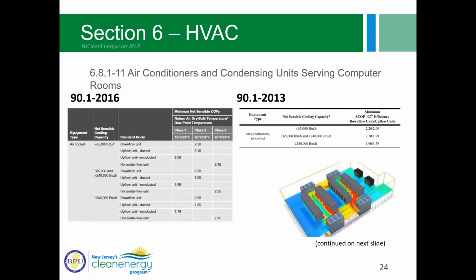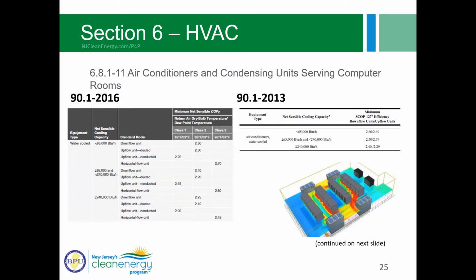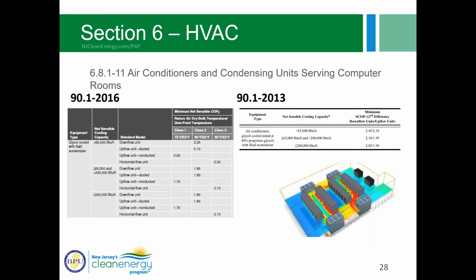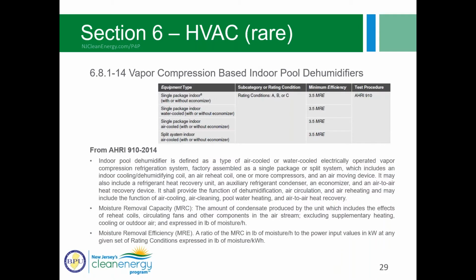that we're specifying. Same table here, this is for water-cooled units. So similar expansion between all the types of units. This is water-cooled with fluid economizer, glycol-cooled, and glycol-cooled with fluid economizer. So you can see also the efficiency ratings improved for the most part. Yeah, so you can just look through as examples to see how those changed in addition to that expansion. So you have to read a little bit between the lines to make sure that the comparisons are correct.